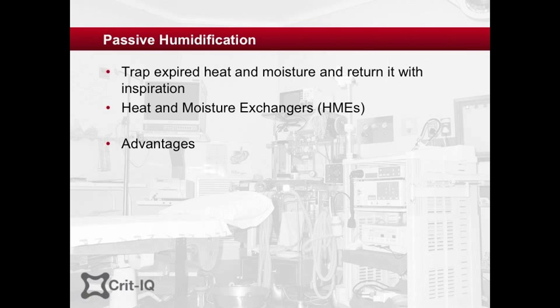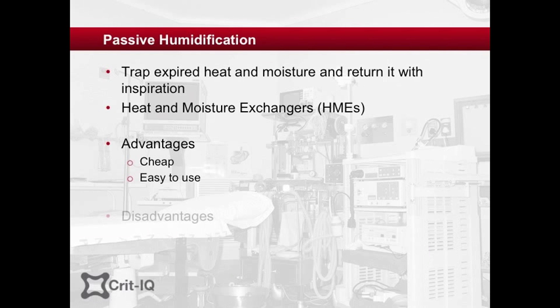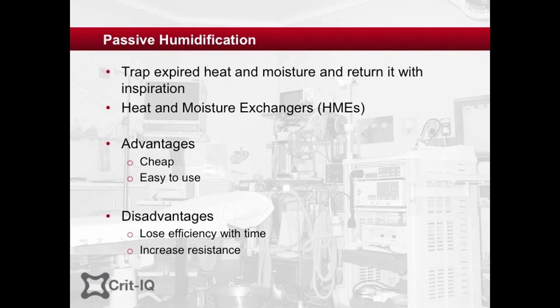The advantages of HMEs are that they are cheap and easy to use, and are very useful for short periods of ventilation. However, as their use is prolonged they lose efficiency and can progressively increase the resistance to gas flow. HMEs also add weight to the tube, which can be a factor in pressure ulceration and tube dislodgement, and they add dead space to the circuit, which can be important particularly in children.